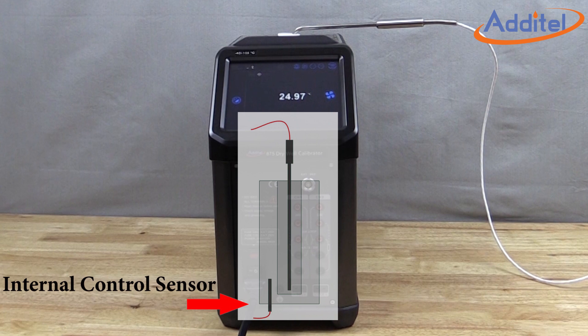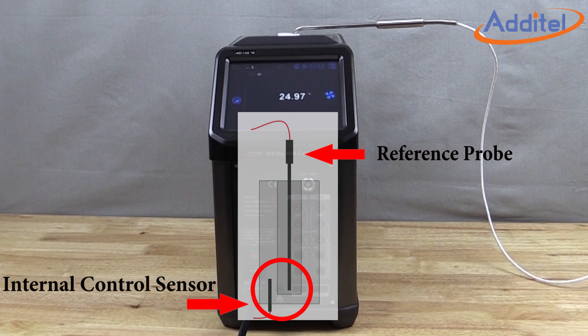During calibration, this robust internal sensor is calibrated via comparison measurement with a reference thermometer. Coefficients are calculated based on the variances and then programmed into the dry well to account for the difference. Additel's new self-calibration feature utilizes the onboard reference thermometer input and a reference probe to provide a turnkey solution for calibration of the dry well.